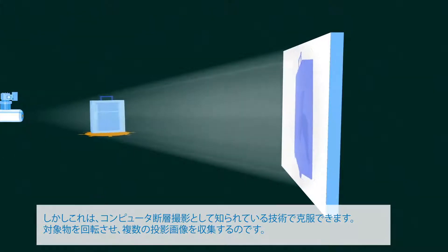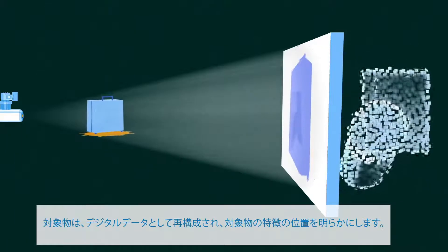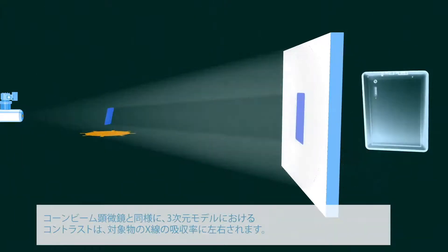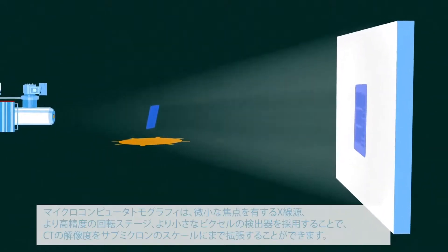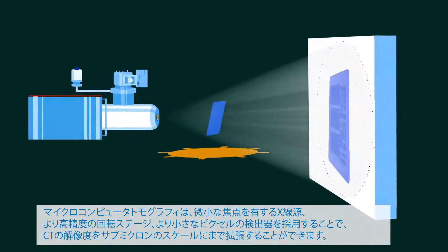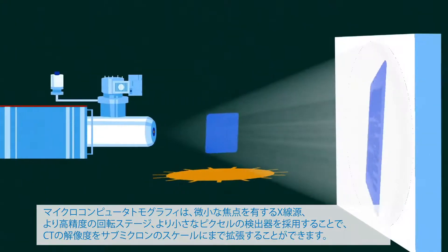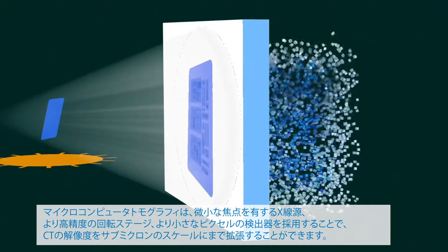Several projection images are collected as the object is rotated. The object is digitally reconstructed, revealing the position of features within it. As with cone-beam microscopy, contrast in the three-dimensional model comes from the absorption difference of the features in the object. Microcomputed tomography extends the resolution of CT into the submicron scale by using X-ray sources with finer focuses, object stages with higher precision, and detectors with smaller pixels.